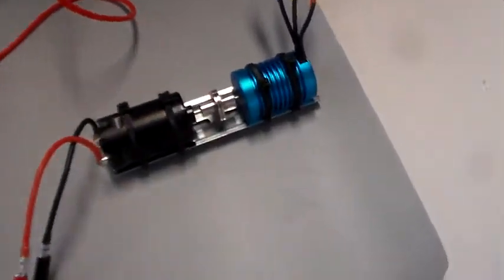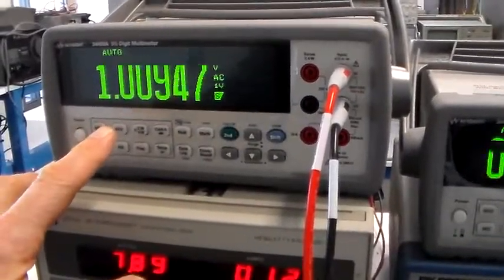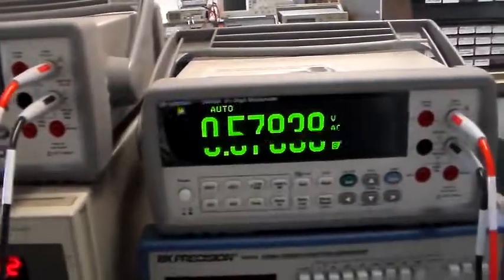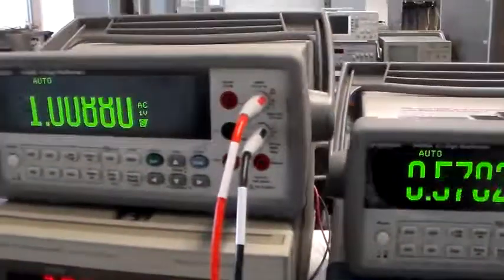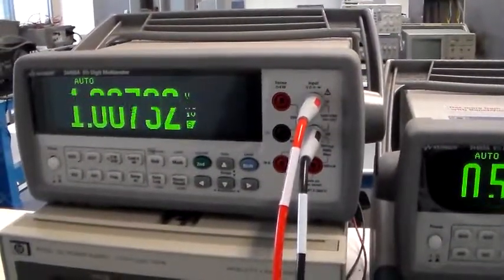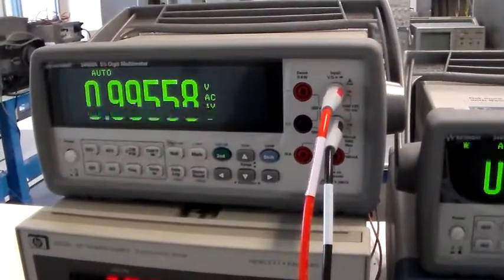You can see in here the motor generator set has started, and currently my line voltage is just over 1 volt, and my phase voltage is slightly over 0.577 that we'd expect. I can try to more precisely adjust this down to 1 volt line voltage by decreasing the speed of my DC motor.